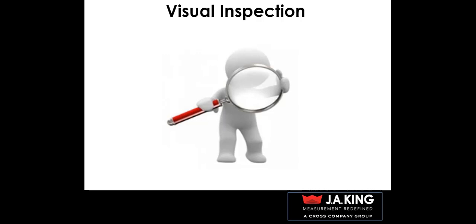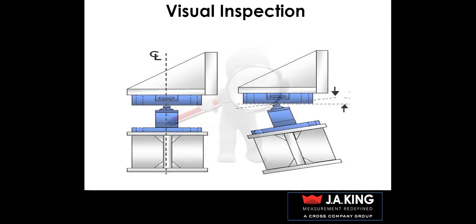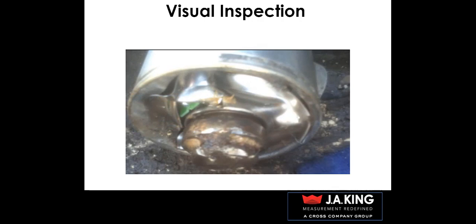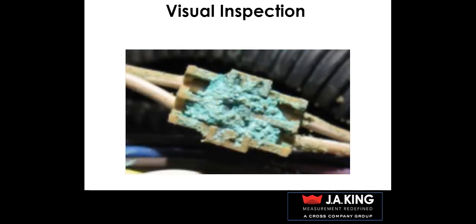Always start with a quick visual inspection before performing any test. Check the mechanical supports, load cell orientation, and mounting surfaces for cleanliness, levelness, and alignment. Check load cells for dents, cracks, excessive wear in the loading area, bending, or buckling. Check the interconnecting cables at the summing box. All cabling should be free of cuts, crimps, corrosion, exposed wires, etc.